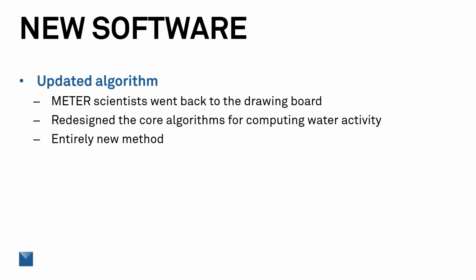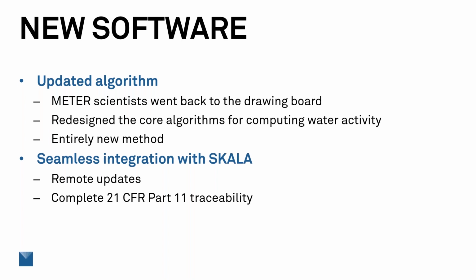And how does the TDL2 integrate with Meter's cloud-based system called Scala? You mentioned Scala before. So what is Scala and why is it important for this new instrument? Yeah, so Scala is our food manufacturing software platform. Now, I say food, but it also ties into other pharmaceutical manufacturing and chemical manufacturing as well. And what it enables our clients to do is to take the quality measurements and to really combine that with the process data that they're already collecting, or we can help to collect that process data. And so it brings in some potential insights into that interaction between product and process that may not have been available to begin with. So the TDL integrates with that. And now what that allows us to do is to provide remote updates. So that's new features, new updated calibration, and also provides a traceable database of your measurements and of the calibration of the instrument itself. And this is 21 CFR Part 11 compliant.